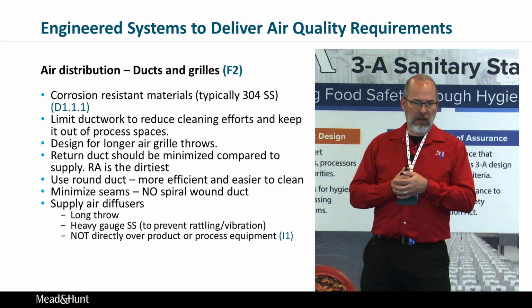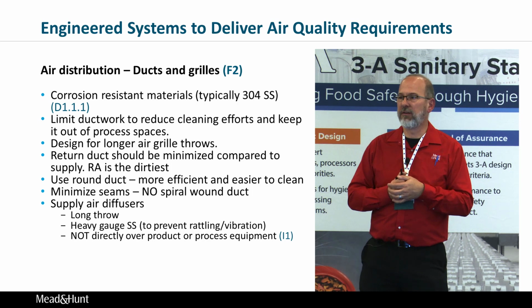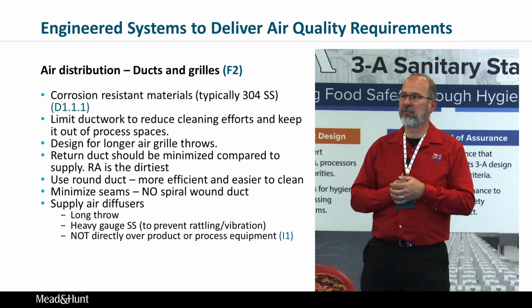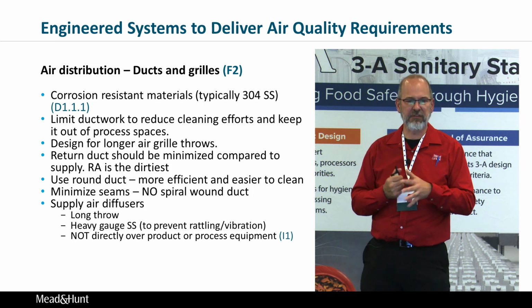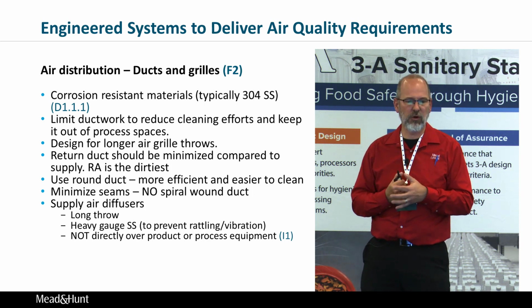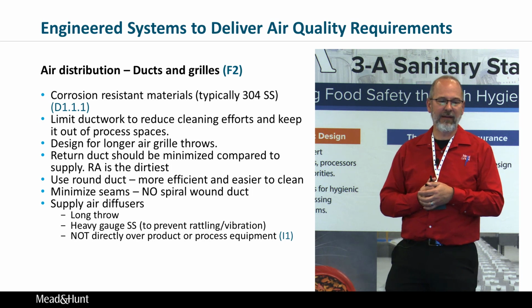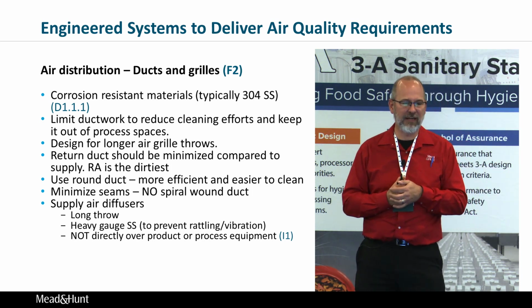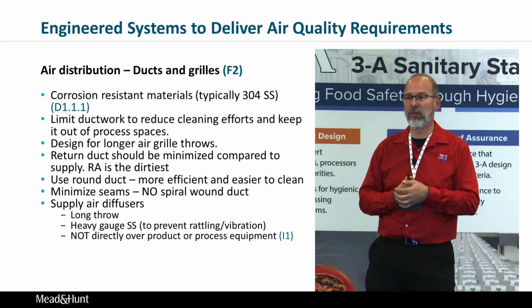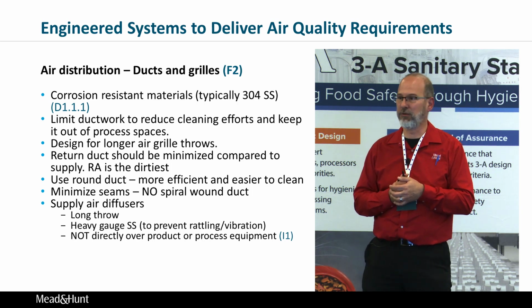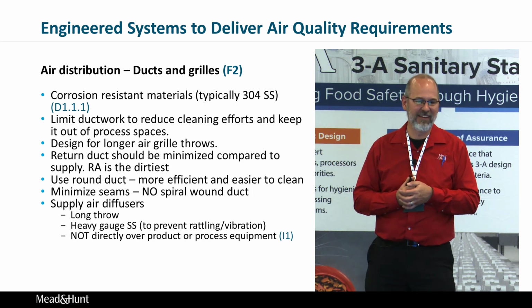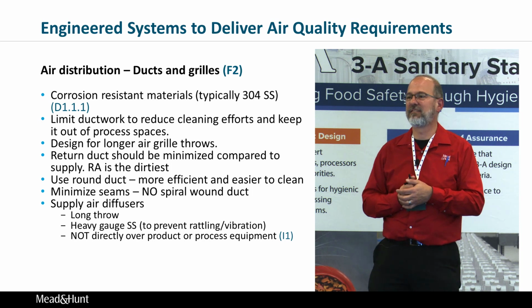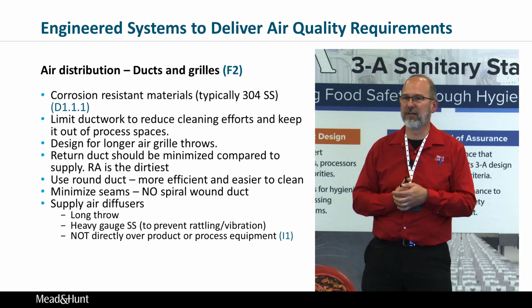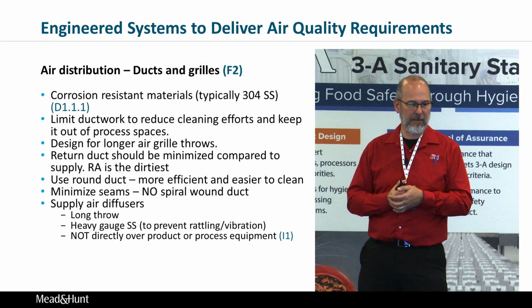I also use round duct whenever possible. It's easier to clean. Most times it's more cost effective to build, and from an HVAC standpoint, it's just the most efficient. So go round whenever you can, round duct. And please, don't let a contractor or designer talk you into putting spiral wound ductwork in a food processing unit, ever. I've seen a lot of that in the past, and it's a terrible harborage element in a system.